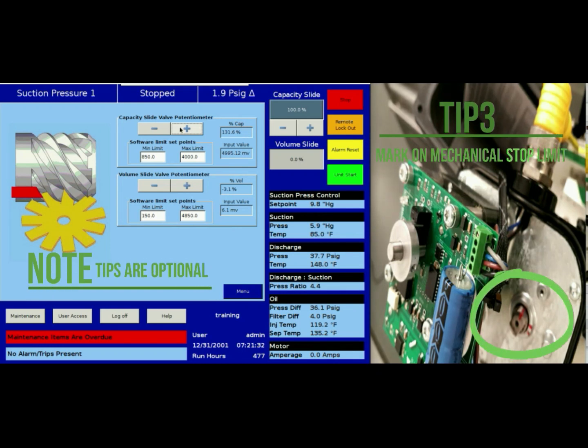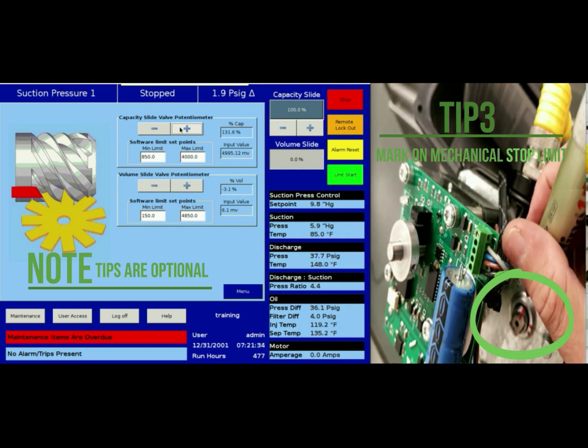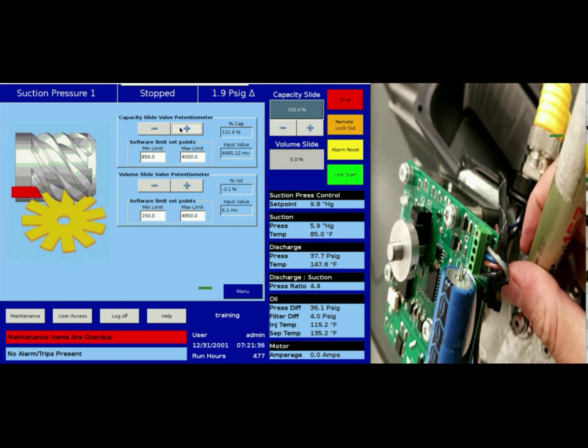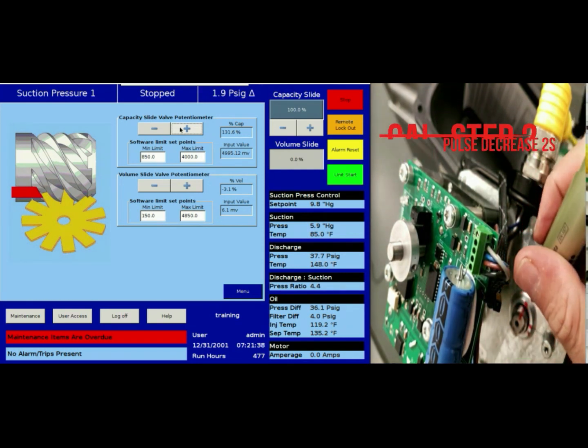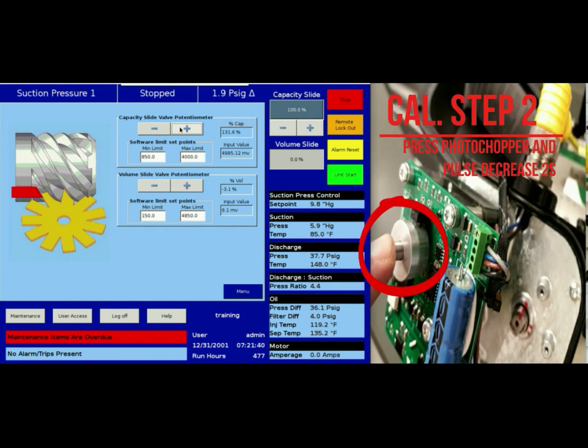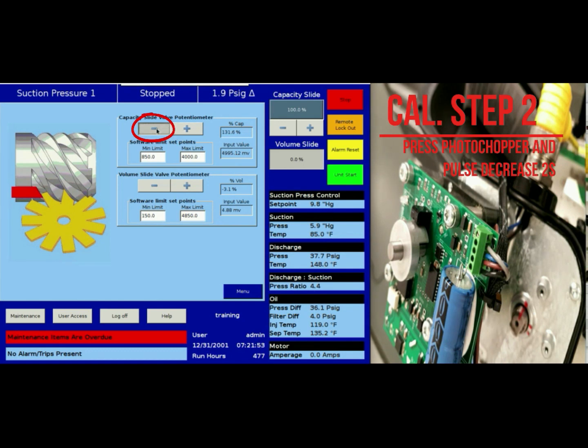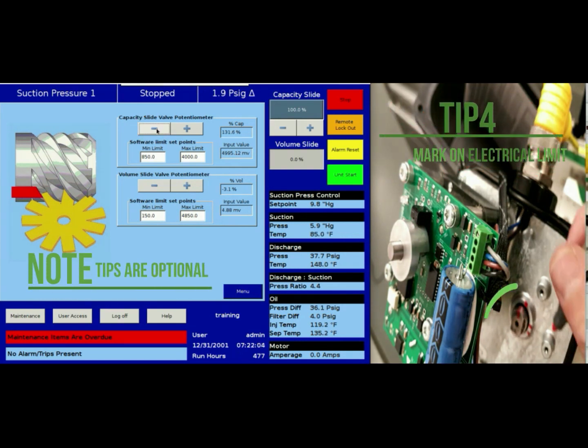Once the actuator has reached its mechanical stop, release your finger from the increase button on the screen and release the tension on the photo chopper the same way we did when we set our minimum value. Push down gently with your finger on the photo chopper, releasing any tension. Once the tension has been removed, we want to pulse the minus decrease button to allow some buffer between the mechanical stop and our maximum limit. Press and hold the minus button for 3 seconds.